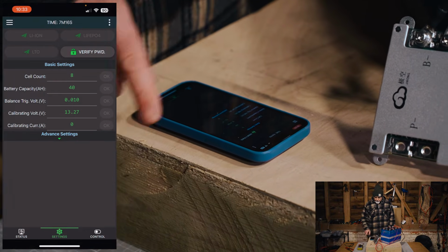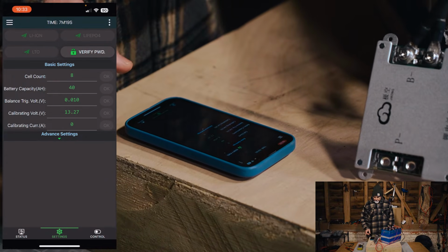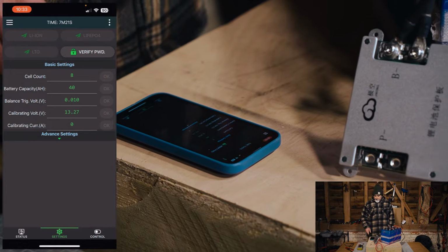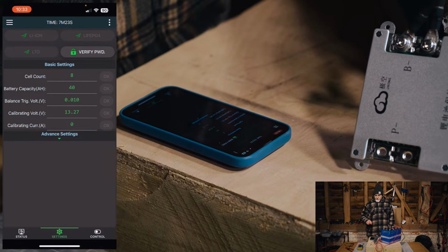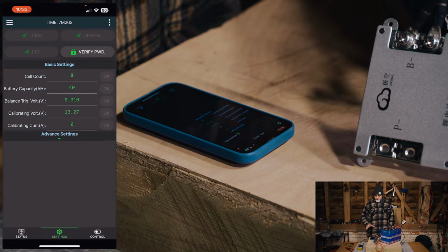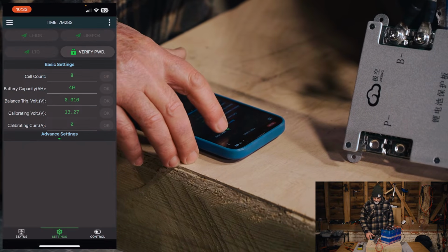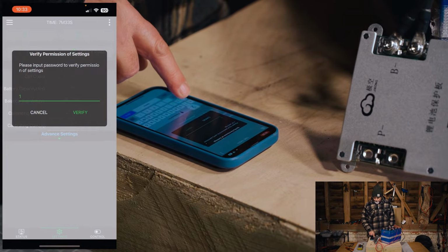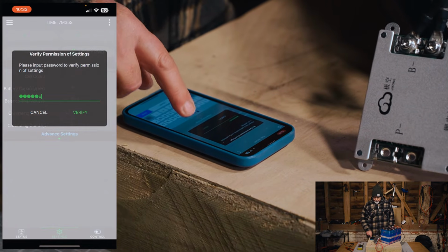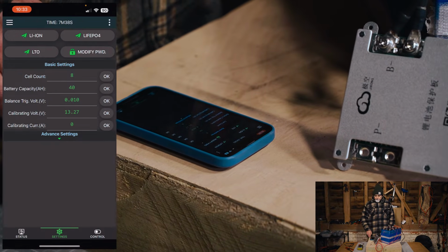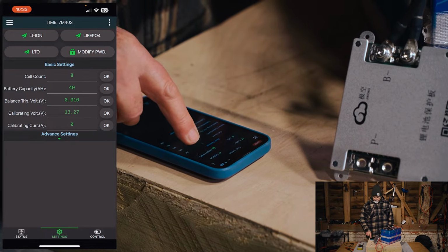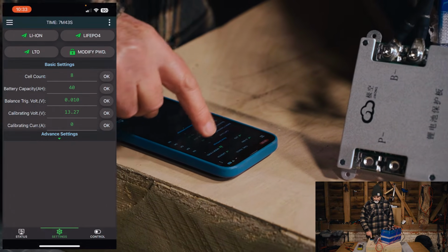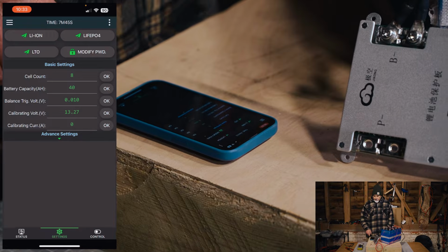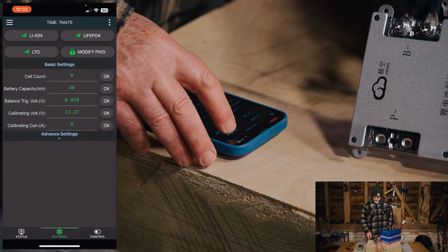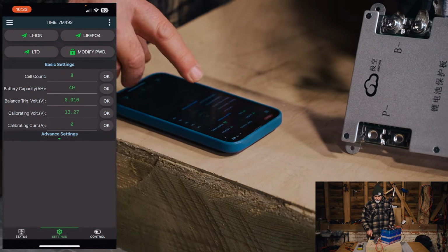So if we go to settings, you can either swipe left or right, or you can just go to settings. Now, the first thing you will need to do, in order to make any change, is to verify the password. So we click on verify password, and the default password is, guess, 1, 2, 3, 4, 5, 6. You click on verify. That's now changed to modify password, and you've got the 3 types of batteries that you could choose from. We could now choose lithium iron phosphate, so let's just click on lithium iron phosphate.